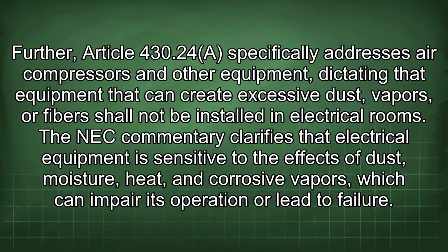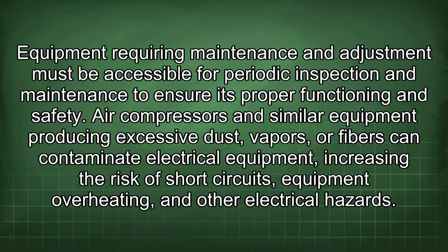Further, Article 430.24 specifically addresses air compressors and other equipment, dictating that equipment that can create excessive dust, vapors, or fibers shall not be installed in electrical rooms. The NEC commentary clarifies that electrical equipment is sensitive to the effects of dust, moisture, heat, and corrosive vapors, which can impair its operation or lead to failure. Equipment requiring maintenance and adjustment must be accessible for periodic inspection and maintenance to ensure its proper functioning and safety. Air compressors and similar equipment producing excessive dust, vapors, or fibers can contaminate electrical equipment, increasing the risk of short circuits, equipment overheating, and other electrical hazards.